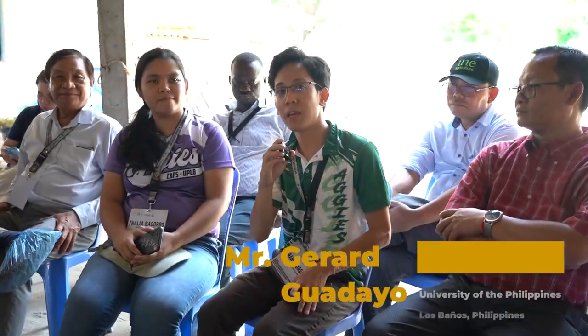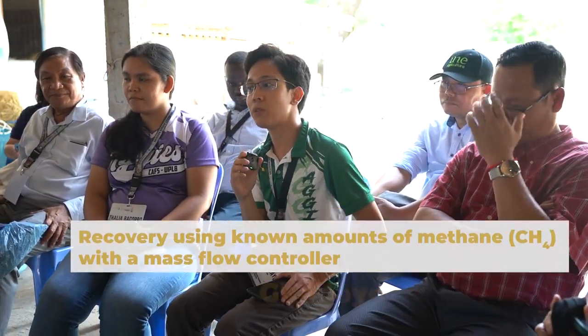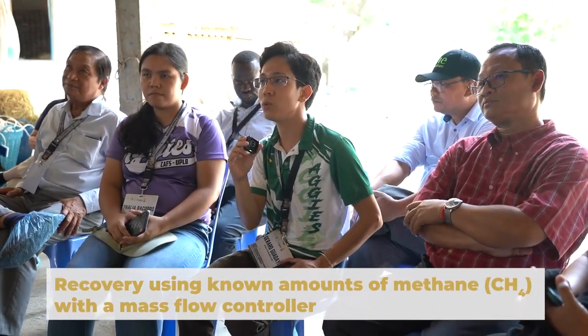We do recovery tests the same as in Indonesia. We use a mass flow controller as well to infuse a known amount at a known rate of pure CH4. We let it infuse the gas for about 2 minutes before we collect about a minute and a half worth of data. So that is going straight up the exhaust, not mixing in the chamber. It goes straight into one of the inlet ports, like we are doing here with CO2. But I think we would all say it is better if we can do the mixing in the chamber. That way, if there are any holes or leakage, we pick up that effect as well.